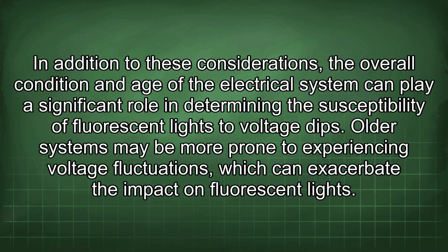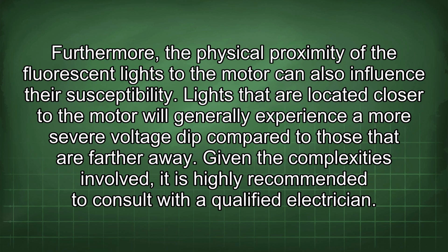In addition to these considerations, the overall condition and age of the electrical system can play a significant role in determining the susceptibility of fluorescent lights to voltage dips. Older systems may be more prone to experiencing voltage fluctuations, which can exacerbate the impact on fluorescent lights. Furthermore, the physical proximity of the fluorescent lights to the motor can also influence their susceptibility.